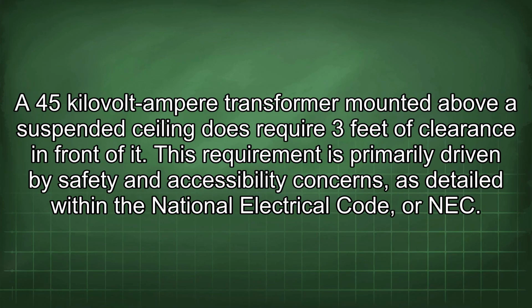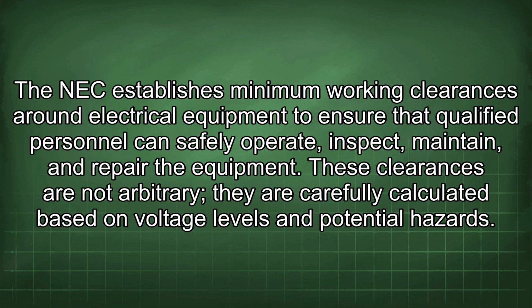A 45 kilovolt-ampere transformer mounted above a suspended ceiling does require 3 feet of clearance in front of it. This requirement is primarily driven by safety and accessibility concerns, as detailed within the National Electrical Code, or NEC. The NEC establishes minimum working clearances around electrical equipment to ensure that qualified personnel can safely operate, inspect, maintain, and repair the equipment. These clearances are not arbitrary, they are carefully calculated based on voltage levels and potential hazards.